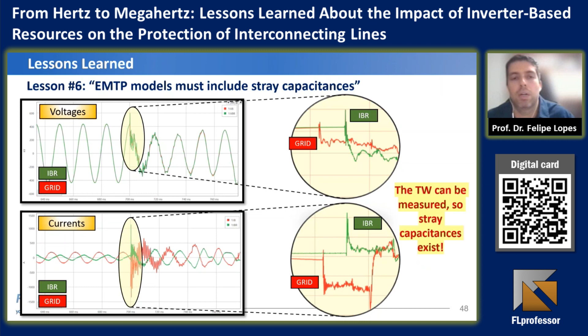Basically, here we have a real record, and we can see that there is a wave reaching the IBR terminal. This is a transformer terminated line. So if the traveling wave can be measured, we can conclude that this stray capacitance exists. This is a recommendation that we have given to people here in Brazil. You can use traveling waves, but before that, maybe it would be interesting to analyze the levels of the stray capacitances at the busbar and across the transformer.